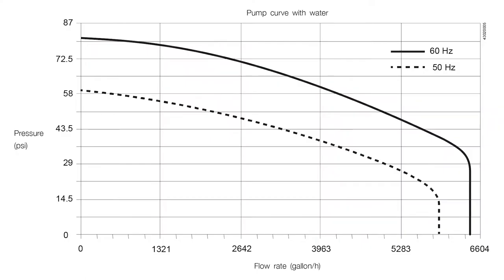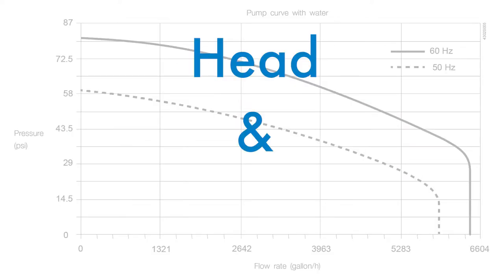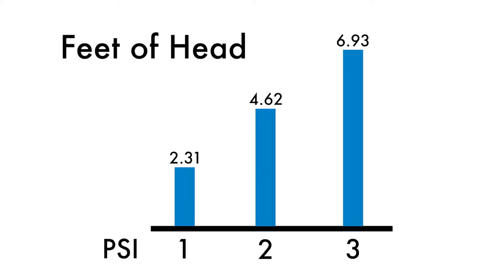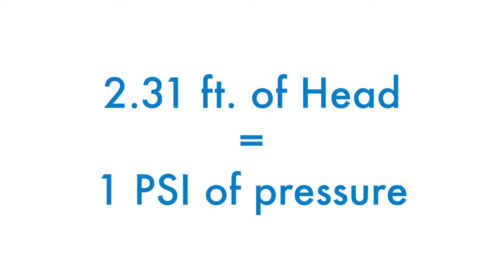A basic pump curve provides two pieces of information about the pump's capacity to move water: head and flow. Head is the height to which a pump can raise water straight up. Water creates pressure or resistance at predictable rates. For example, every 2.31 feet of head equals 1 psi of pressure.